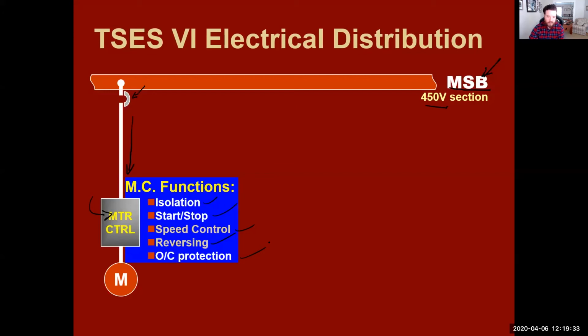So for isolation, what are we isolating, and from what to what? Let's start with the first thing: what are we isolating from? Other motors you have coming off the line, or any other lines coming off the 450 section. So you're isolating from your main switchboard to your motor controller, utilizing this breaker right here.